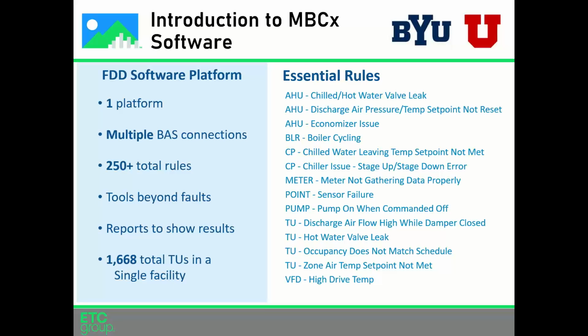For instance, if we have a chilled water valve and the command says it should be closed, but we see a temperature drop across the coil, that's an indicator there might be a leaking chilled water valve, and we can see a fault come out of that rule. So faults are really important to find. When you have so much data streaming into your platform, it's really hard to manually go through and find all of those discrete problems or inefficiencies that are happening. That's what faults can do for us.